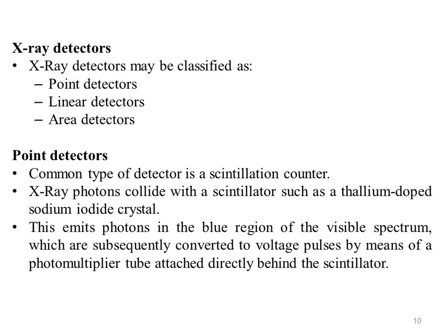Now we will discuss different detectors used in X-ray diffractometers. X-ray detectors may be classified as point, linear or area depending on whether they record the diffraction pattern in 0, 1 or 2 spatial dimensions. Point detectors must be scanned to measure the diffraction pattern, whereas linear or area detectors can be fixed.